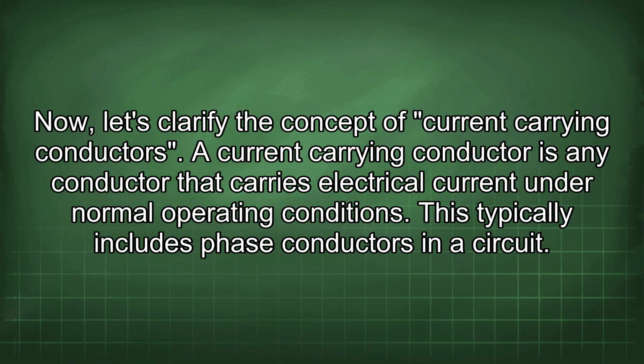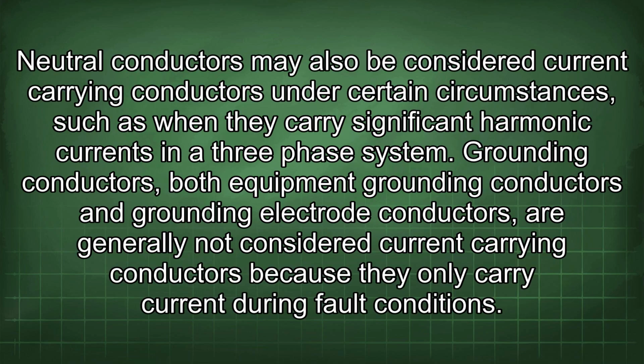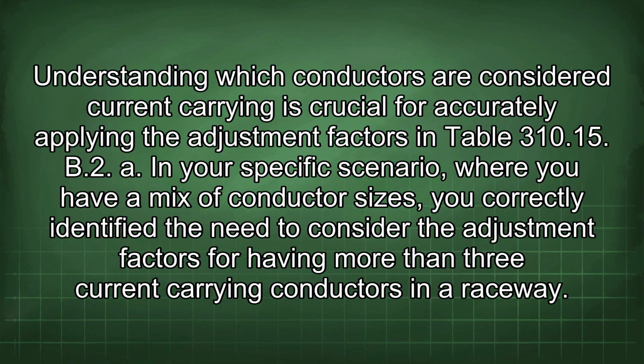Now let's clarify the concept of current carrying conductors. A current carrying conductor is any conductor that carries electrical current under normal operating conditions. This typically includes phase conductors in a circuit. Neutral conductors may also be considered current carrying conductors under certain circumstances, such as when they carry significant harmonic currents in a 3-phase system. Grounding conductors, both equipment grounding conductors and grounding electrode conductors, are generally not considered current carrying conductors because they only carry current during fault conditions. Understanding which conductors are considered current carrying is crucial for accurately applying the adjustment factors in Table 310.15 B2.